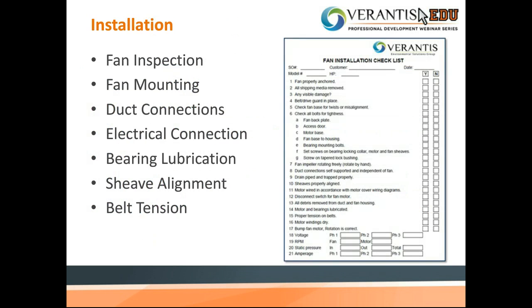So all right, I've got this fan. We've received it. Everything checks out okay. What's the next step? How about we install this thing? Let's put this in the field and see what we can do. So with installation, there's going to be a fan inspection. You've got fan mounting, duct connections, electrical connections, bearing lubrication, sheave alignment, and belt tension. All of these things are key to go through before you put this fan in service. There's a nice little checklist right next to you that goes over some of this information. It's great to have before you start up a fan. Go through the checklist and make sure you hit everything. We'll dig into each one of these line items a little bit further, and that's what the next handful of slides are going to do.